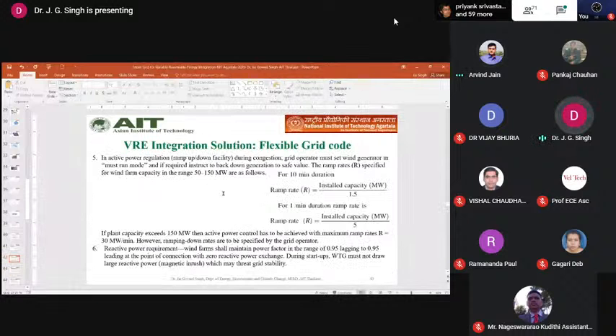You can see that for active power regulation, with ramp down and ramp up facilities, during congestion the grid operator must set the wind generator in must-run mode and, if required, instruct it to back down generation to a safe value. The ramp rates are determined for a 10-minute duration: installed capacity divided by 1.5. For a 1-minute duration, the ramp rate is installed capacity divided by 5. This is for a 50 to 150 megawatt wind farm. But if the plant capacity is more than 150 megawatt, then active power control has to be achieved with a maximum ramp rate of 30 megawatt per minute.